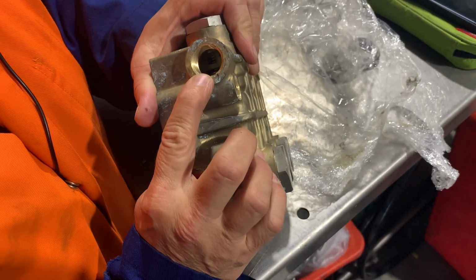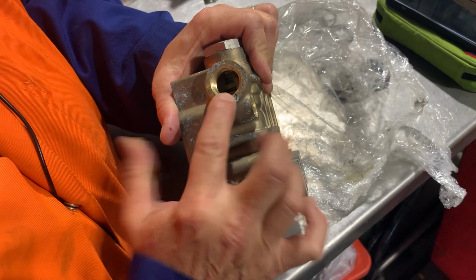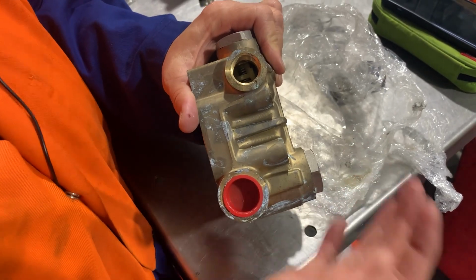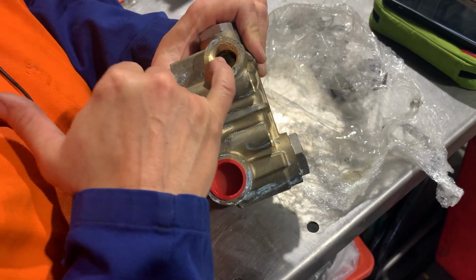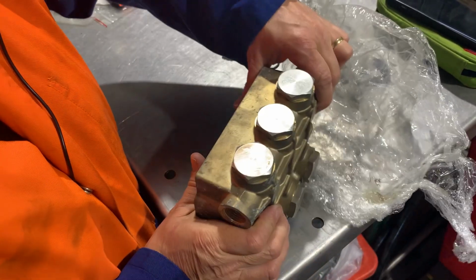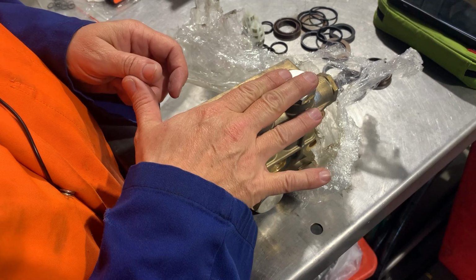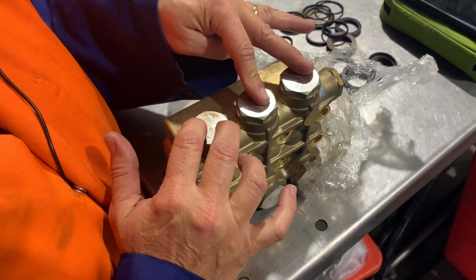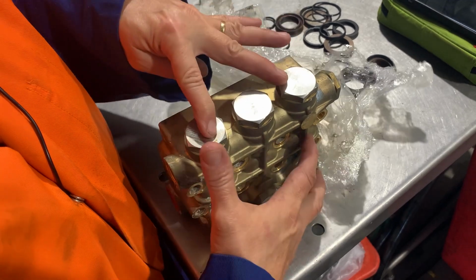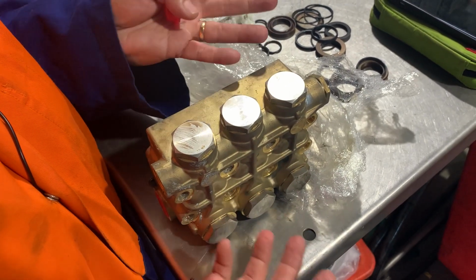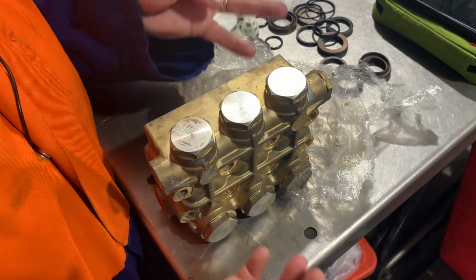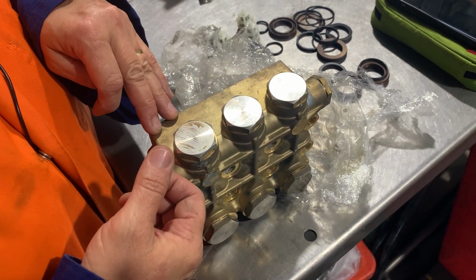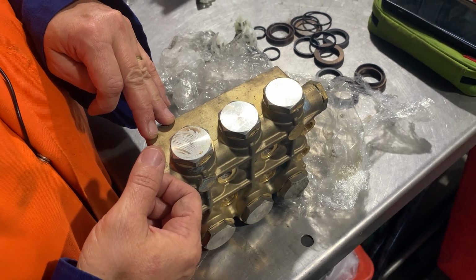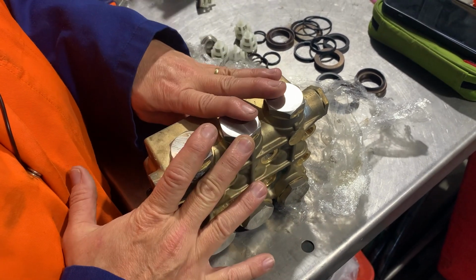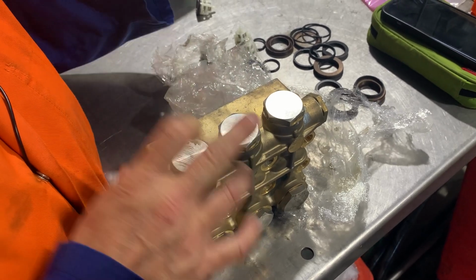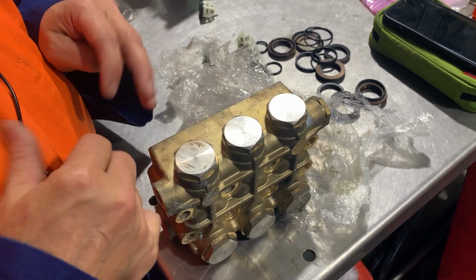In that port there, you'll see there's a valve and it looks good. I usually look through my ports whenever I'm checking anything, if it's off, like if the unloader's off, for instance, because it can show you the condition of it. The other thing is, you can change these valves without removing anything. You just remove these caps. It's a 32mm socket. We actually have a video on how to do that. I would change these on site in about 15 minutes myself, pretty quickly. They're really straightforward. You seat your O-rings, seat your valves. There is a special tool that you can get from us that is easier than using ball nose pliers. So that's your valves, and you don't have to replace anything else. If you have to fix it on the run, you don't have to do everything all at once. But your valves are pretty critical.